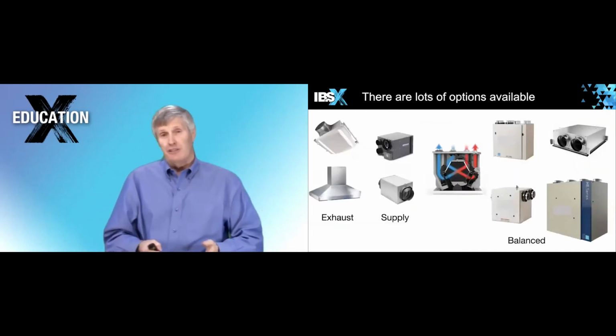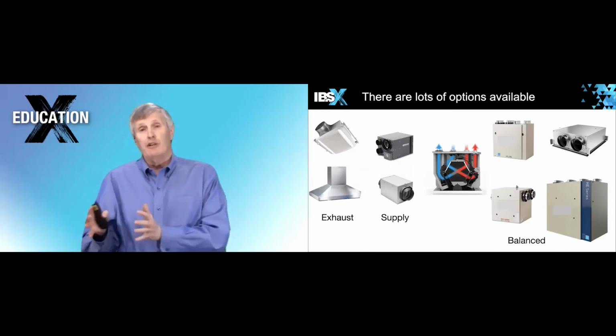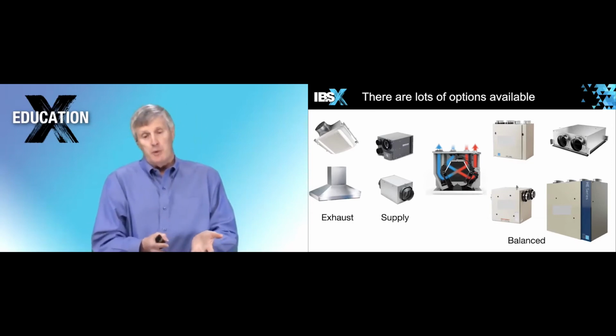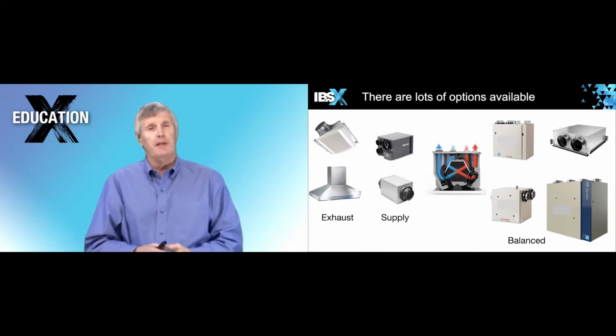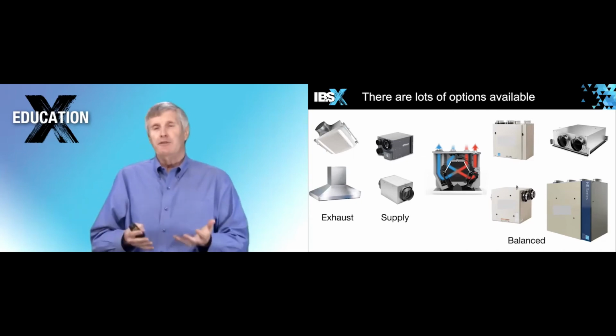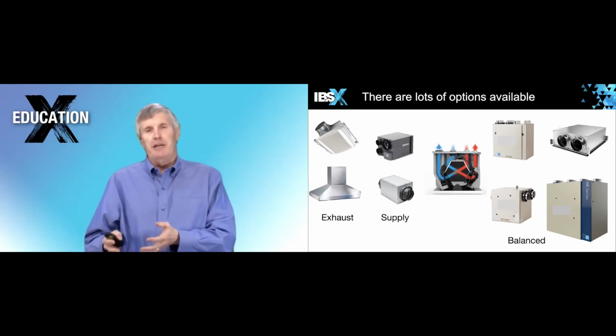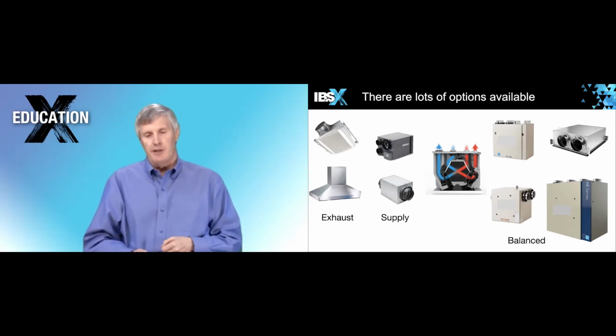And there are lots of options out there. You guys would know the bathroom fan and range hood market, tons of options if you want to do exhaust only, but you're going to go to balance. Or by all means, go to supply only ventilation. There's some good materials on the market as well. But lastly, think about energy recovery ventilation. And the good news is there's 3 or 4 really good, solid North American manufacturers that are building equipment with dozens of different models. Some are top port, side port, to give you duct configurations that you can install pretty much anywhere, in a ceiling space, in a closet, down in a basement next to the furnace. There's really no excuse for not looking at balanced ventilation with energy recovery these days.